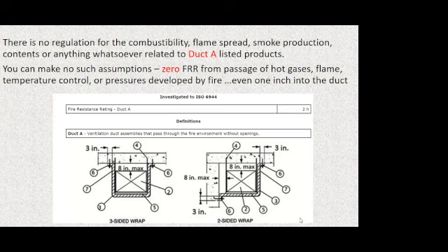In the world of fire rated duct systems, the steel duct, its flanges, its seams, and its external and internal reinforcement are the backbone of the assembly. They are what hold it up in the air, just like the steel stud holds that drywall up. But the drywall is no more fire rated without the stud to which it's attached and the ability of that stud to hold the wall up for 2 hours than a fire rated duct system is capable of being called fire rated because of what happens to be on the outside if what's underneath can't support it for 2 hours.